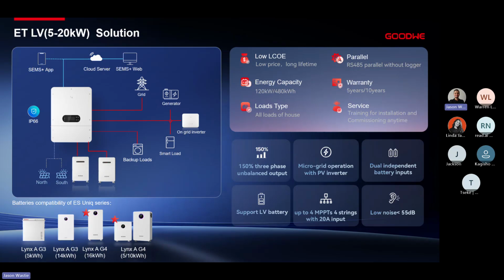With these inverters, we can parallel up to 10 of them and run them in on-grid or off-grid operation, paralleling them with an RS485 cable and a CAN cable between each inverter. And the same as all of our other inverters, we have a 5-year warranty with an extension up to 10 years on the inverter when using any of our GoodWe batteries.